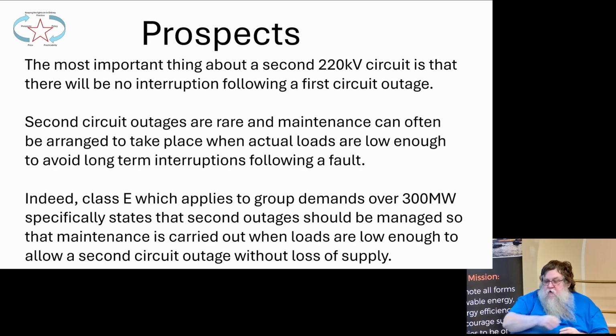Most important thing about a second 220 kV circuit is that there will be no interruption following a first circuit outage. Second circuit outages are rare, and maintenance can often be arranged to take place when actual loads are low enough to avoid long-term interruptions.